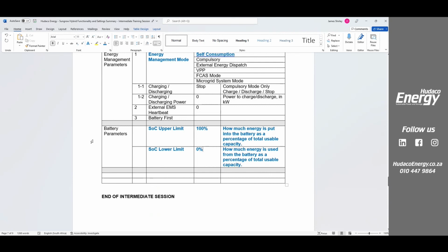This applies at all times when there is no grid present. The reserve state of charge is a limit that comes in between these two limits that says the amount of energy that you need to save for load shedding scenarios. Okay, and those are the parameters.